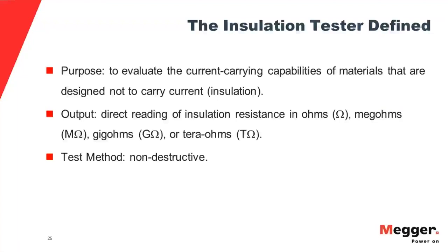The purpose of the tester is to measure insulation. That is to say, the components in electrical equipment that are not current carrying, that are there to retard current and keep it directed in the circuitry and not going to ground, which leads to malfunction, but more importantly, it also represents a danger, a potential danger to the operator.